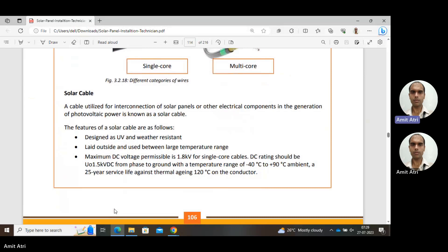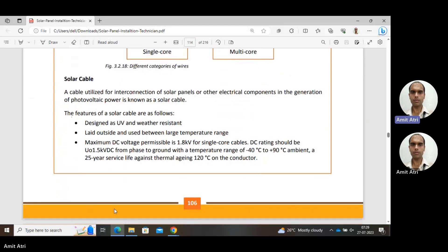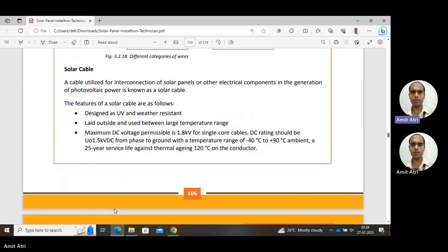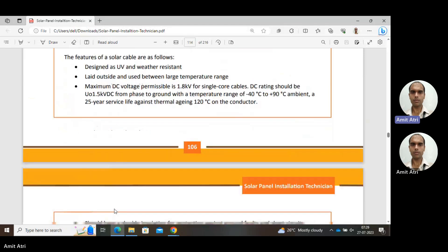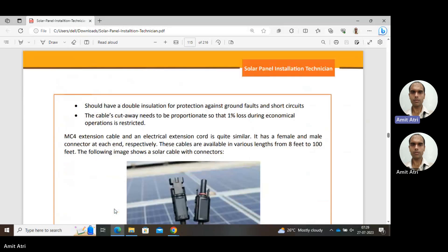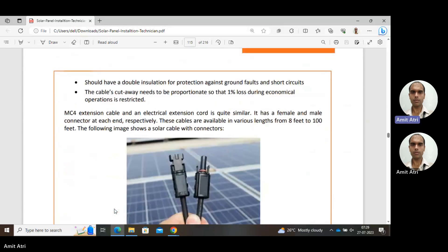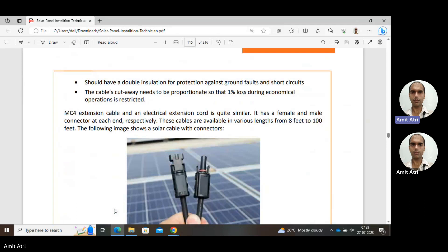Temperature range is approximately minus 40 to 90 degrees Celsius, which we usually have in our locations. We should have double insulation for protection against ground fault and short circuit. Proper insulation should be maintained with no short circuit and no ground connection. Ground fault means leakage of current to ground should be minimized. If wire is not properly insulated, there will be leakage to ground.